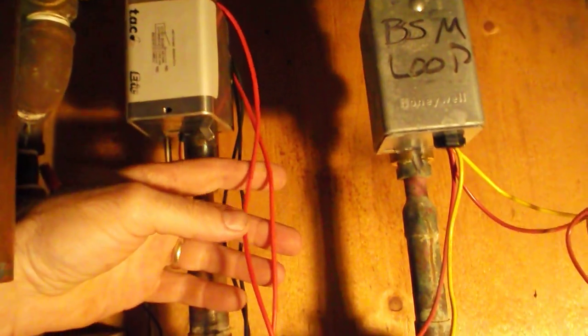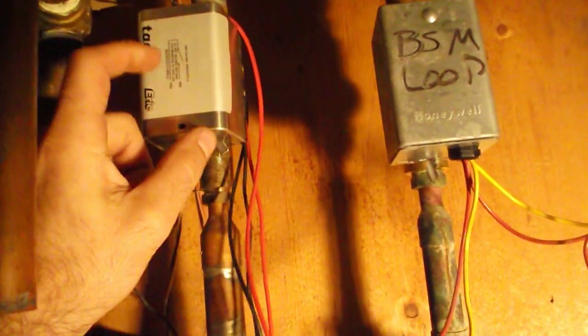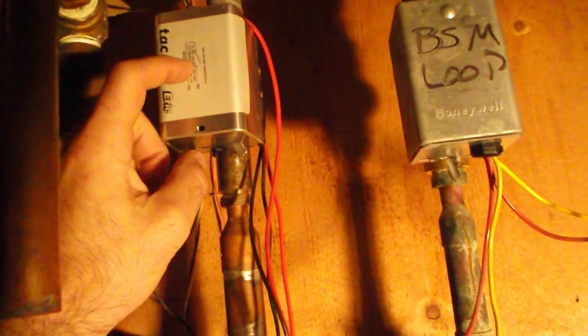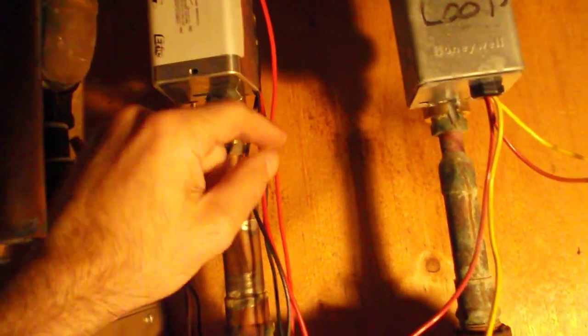one of the connections heads back to a terminal block in the heater. These other two connections, the two red ones, are connected to a micro switch inside the zone control, and when the valve fully opens, these wires activate a signal to the heater control unit that says, hey, the valve is open, the pump can start. So this is the circulating pump. It pumps water down into the bottom of the boiler, and then water comes out and up through the zone control and up through the rest of the house.